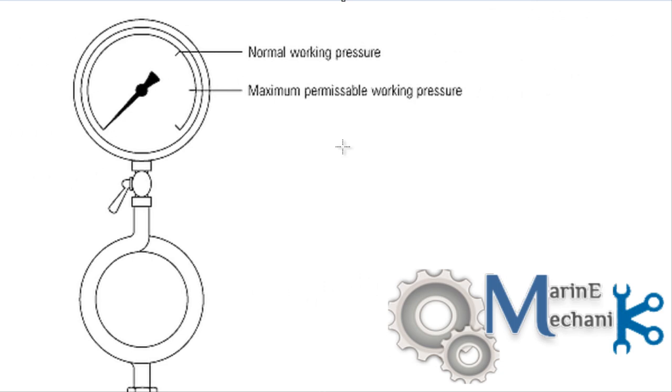When you go in front of an auxiliary boiler on board our ship, the pressure gauge tapping will be taken from the boiler and this will have a curved structure like this. And then this goes to the pressure gauge with a cock or a small valve. And this structure is called as a loop which serves the purpose of siphon tube.